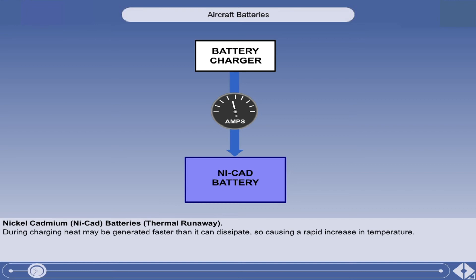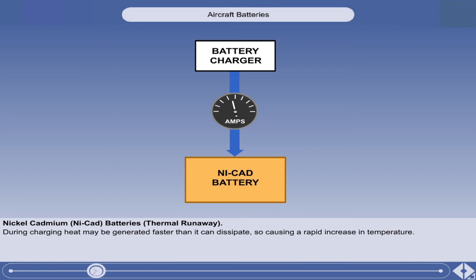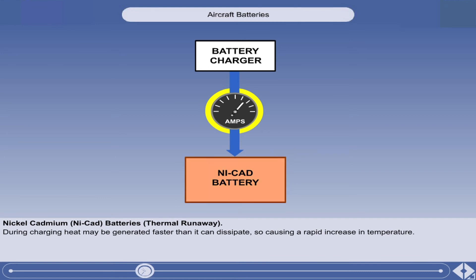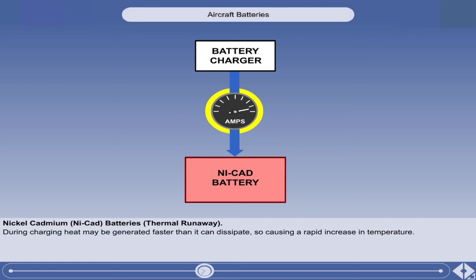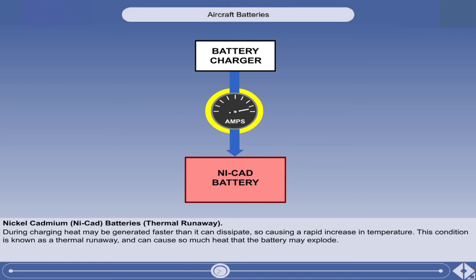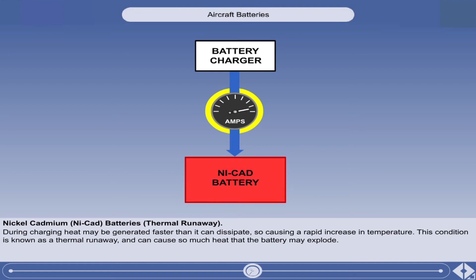NICAD batteries can have a problem with the amount of heat generated during charging. In certain conditions, heat is generated faster than it can dissipate, causing a rapid increase in temperature. This has the effect of lowering the effective internal resistance of the cells, thus allowing an ever-increasing charging current and subsequent increase in temperature, which, unless checked, leads to the total destruction of the battery. This condition is known as thermal runaway, and can cause so much heat that the battery may explode.